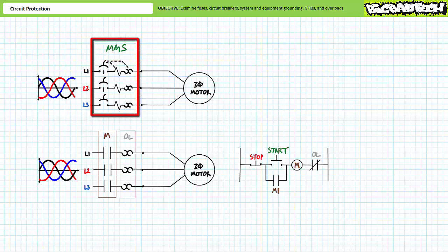Here's a diagram of a three-phase manual motor starter with integrated magnetic and overload elements. You'll note the schematic symbol is almost identical to a circuit breaker. Here the overload elements serve to detect sustained current draw and tells the contacts to break connection. Here's another system incorporating an overload relay in series with a magnetic contactor. Again, the overload elements only serve to detect sustained current draw. When this occurs, the overload relay tells the contactor to break connection via means of pilot control known as ladder logic. We'll examine ladder logic and motor control in later lectures.